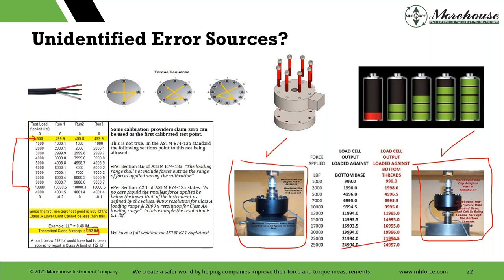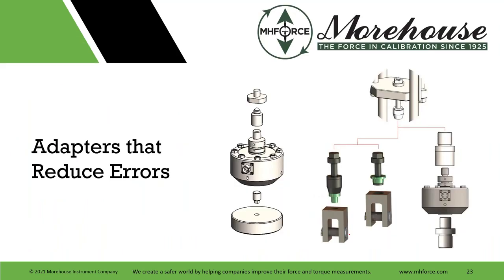So if you're adding 0.012%, that is a bias. That's in addition to the uncertainty that you're claiming. If you're claiming 0.03, have that 0.012% error, chances are you're really 0.042, and that's where proficiency tests and other things will come up and likely show it.